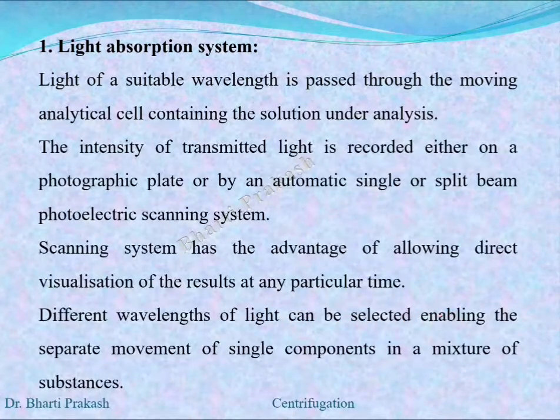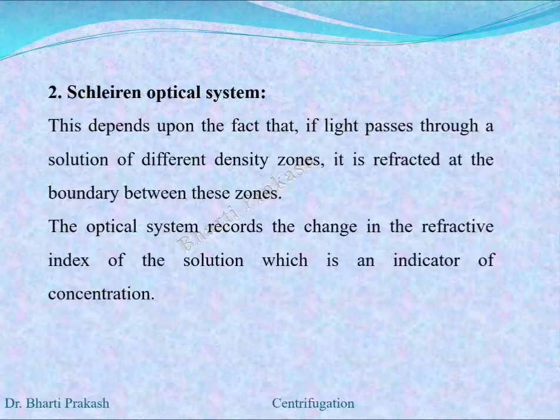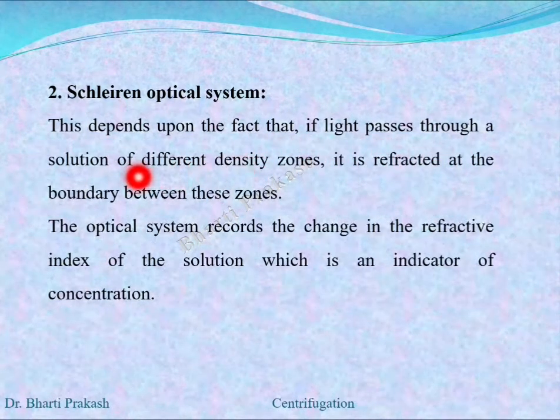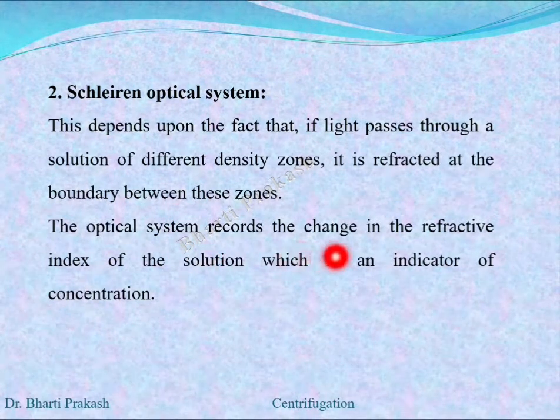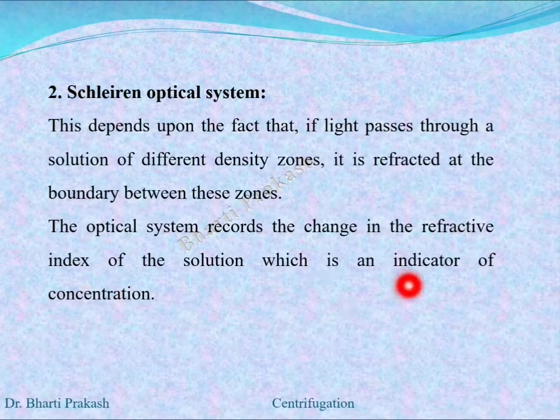The second type is the Schlieren optical system. This depends upon the fact that if light passes through a solution of different density zones, it is refracted at the boundary between these zones. The optical system records the changes in the refractive index of the solution, which is an indicator of concentration.